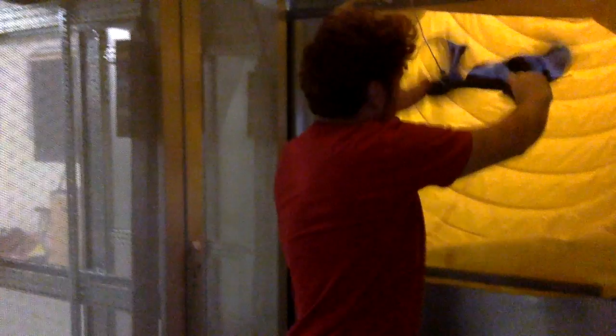Hot air or maybe moderately warm air. We're using a lot more air than we need to actually cool the machine, so it doesn't end up being that hot. And it goes through quite fast. It should be about 14 meters per second through these ducts. And you have to be a little bit careful with small objects or light objects, because if you don't, you very well could lose your shirt. So that's our cooling system.